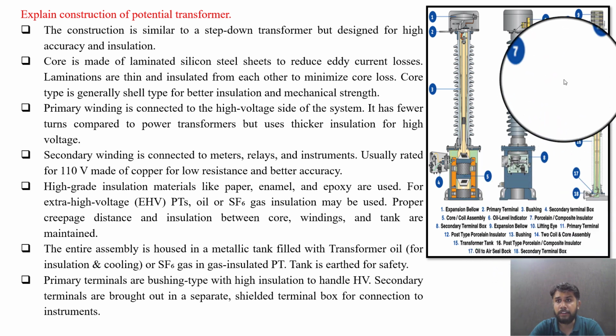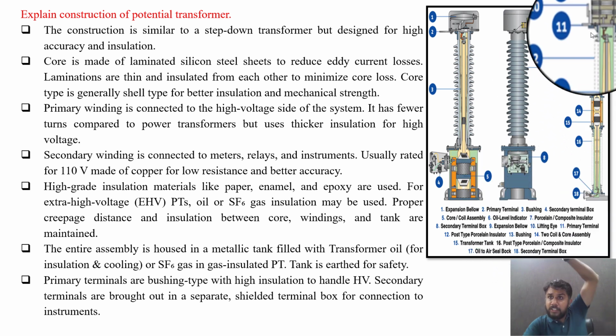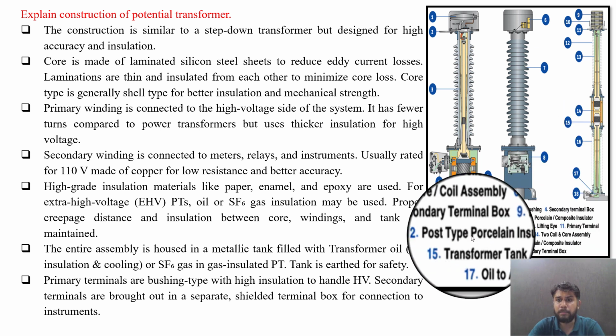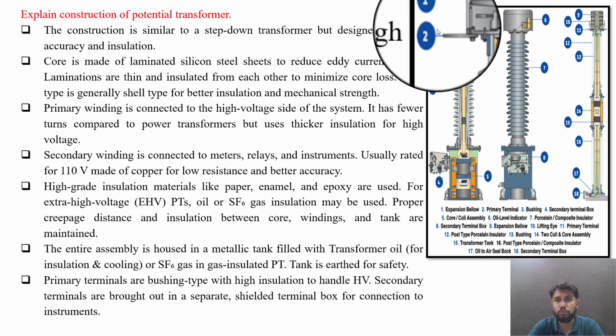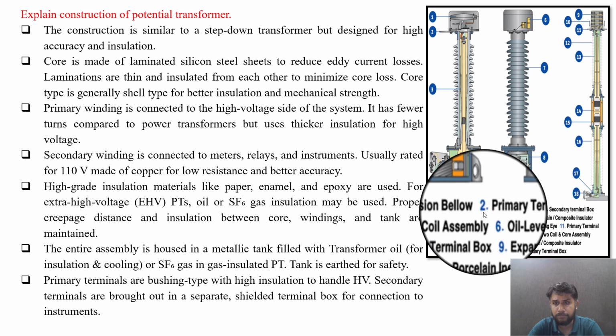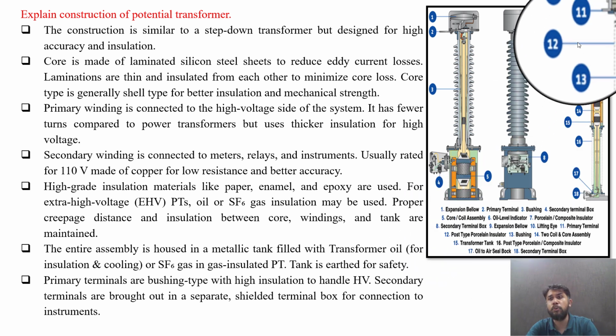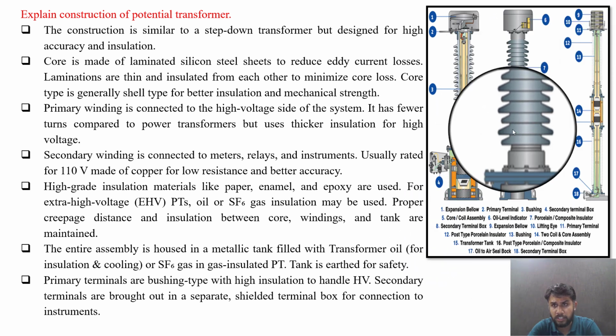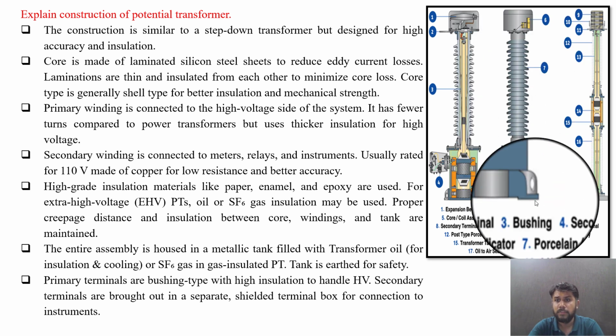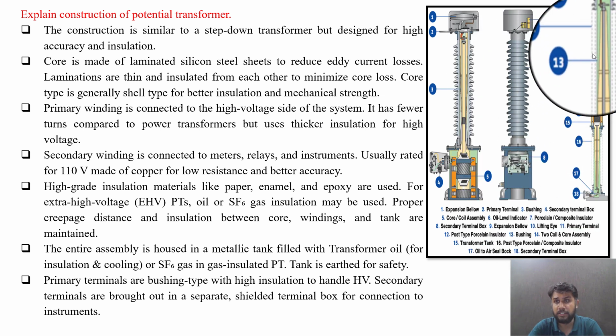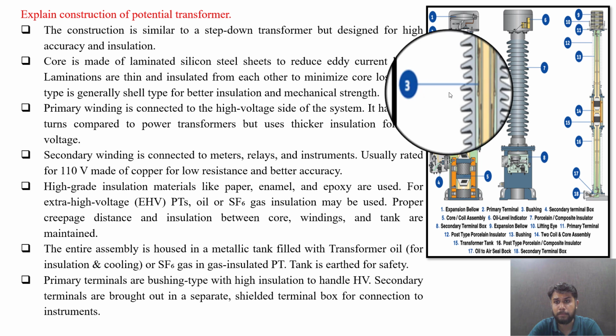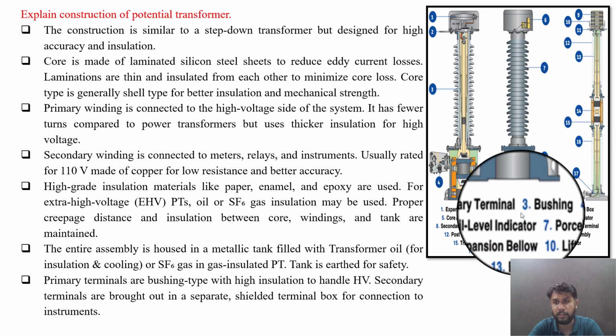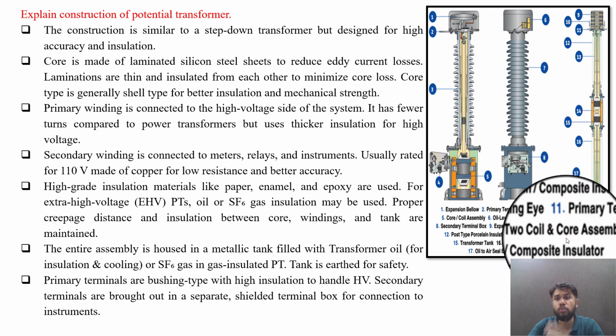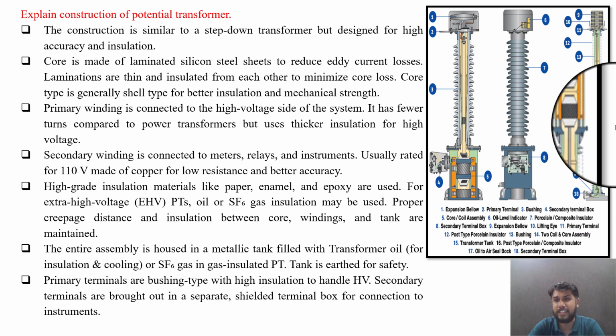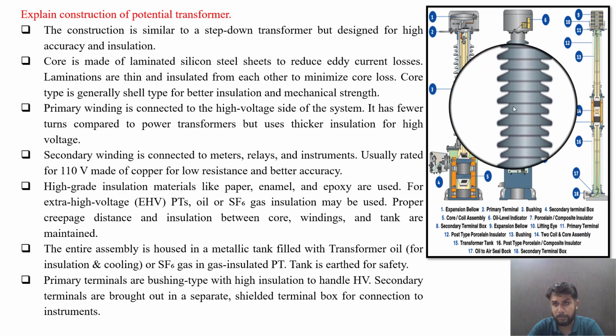Number 10 is the lifting eye where you can lift the PT. 11 is the primary terminal which is also shown with the number 2 here. 12 is the post type porcelain insulator that is shown as number 7 here. 13 is the bushing. This is the bushing that is marked with terminal number 3. 14 is the core or coil assembly. Here it is in between this.